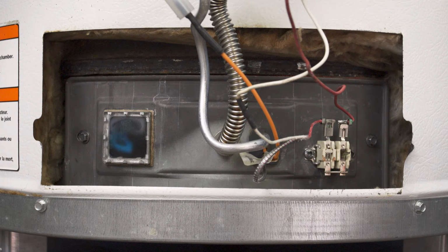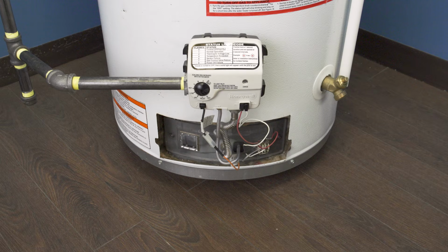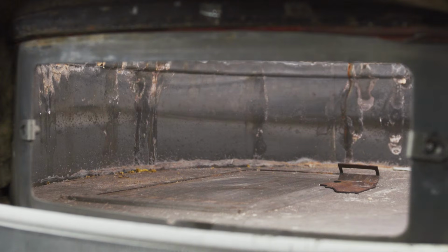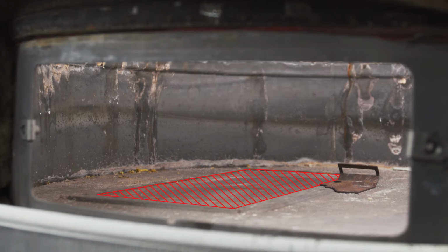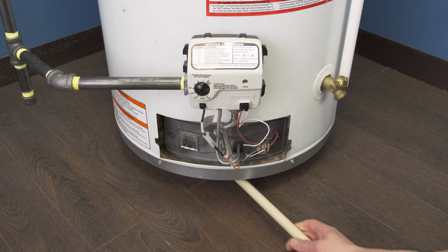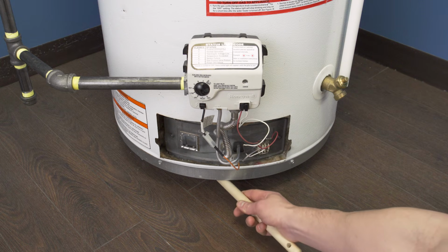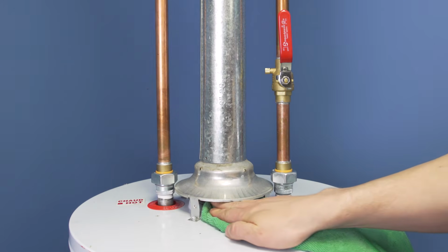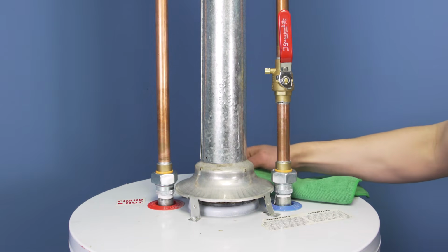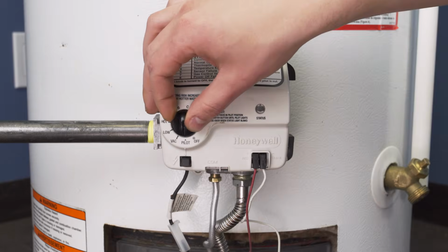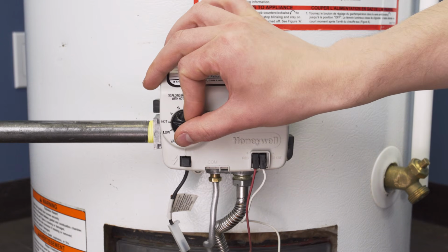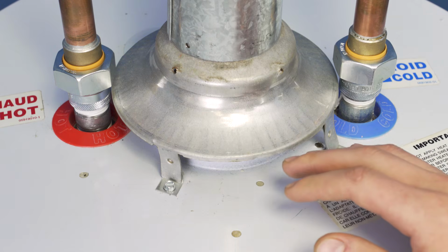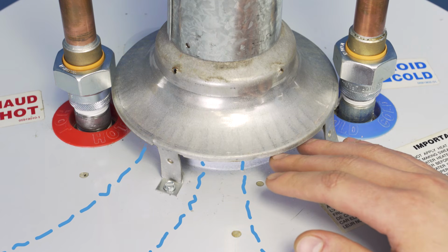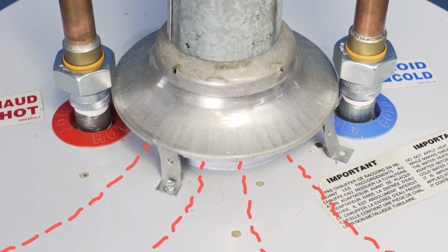If the pilot keeps on going out or the thermal switch keeps tripping, then it could be an airflow issue. Dust can accumulate under the tank or in the flame arrestor screen that supplies air to the burner. This should be cleaned as part of regular maintenance by using a long brush. Additionally, check the flue opening above the tank, making sure it's free of any objects or debris. You can check the airflow by doing a draft test. Turn the main burner on. You should feel cool air being pulled into the vent hood. If you notice warm air coming out of the vent, then it's best to call a technician.